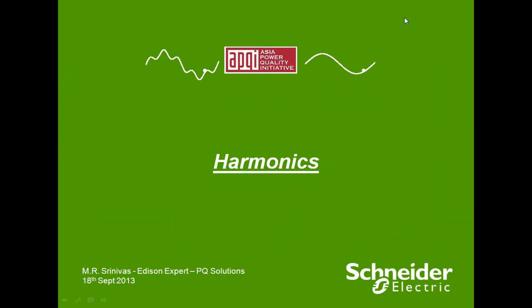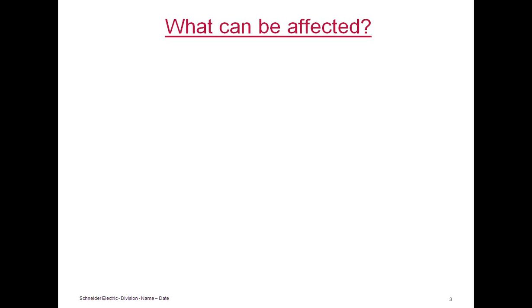Before going to the case studies and practical things, let's go briefly into why harmonics matter. What are the driving factors for harmonics in industry applications? There are three driving factors, three pillars that drive harmonics. Number one is the tariff. Many supply authorities have imposed a tariff on harmonics. That means if harmonic levels are beyond some level, maybe the IEEE 519 standard or some other standards, there is a penalty on this aspect. The second pillar is CO2 emission. If harmonics are beyond certain limits, a consumer will have more energy consumption because of so many reasons.